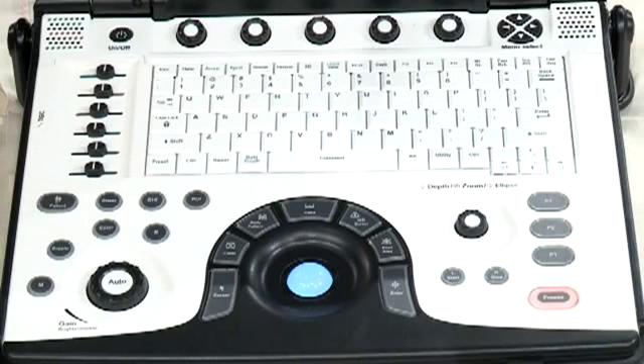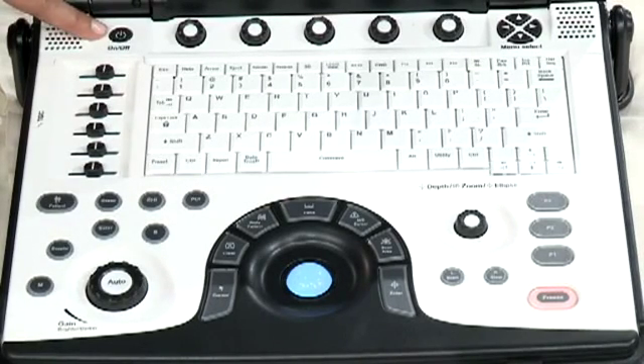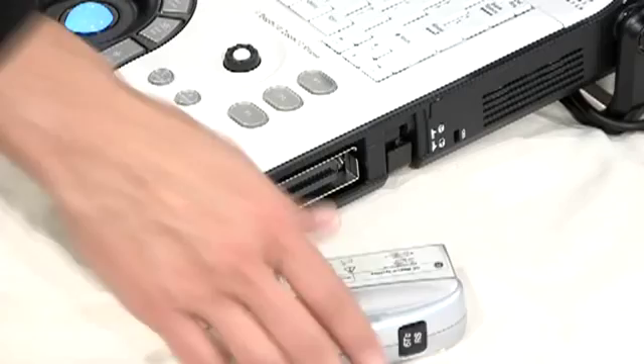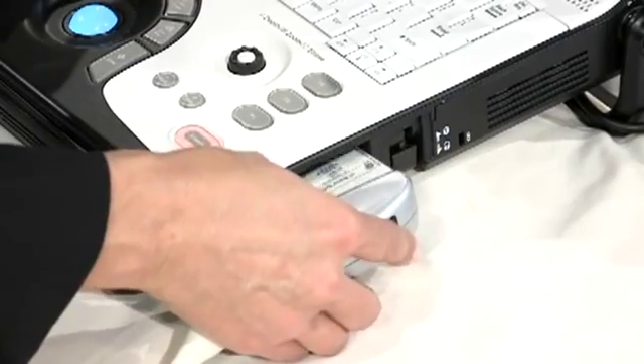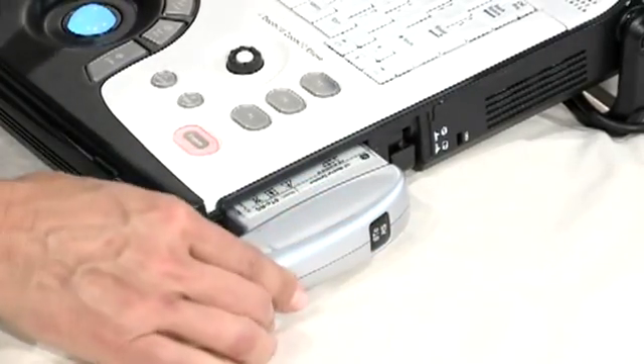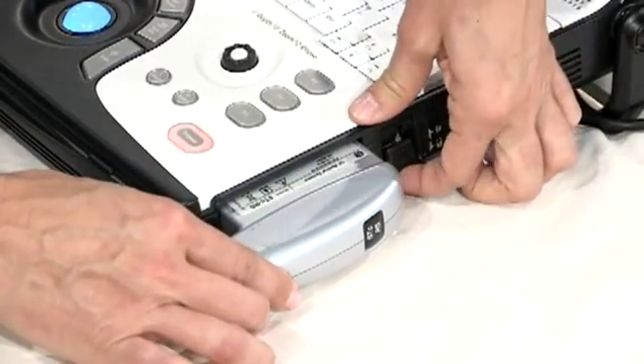To power the LOGIQ E on, use the on-off button on the upper left-hand part of the keyboard. To connect the transducer, take the RS connector directly into the port and pull the lever upward to lock the transducer. After the appropriate probe has been connected and selected, the scan system plane position will automatically calibrate.